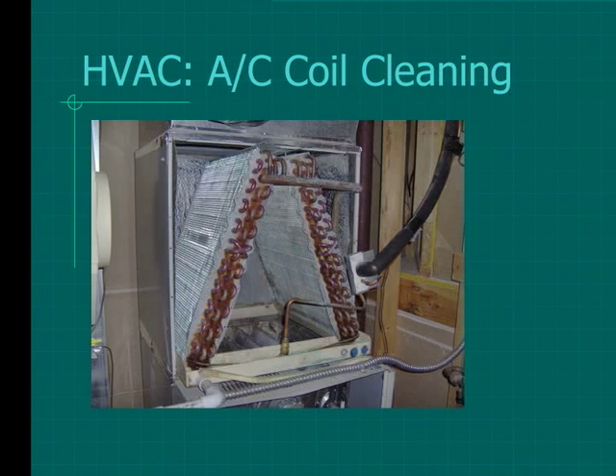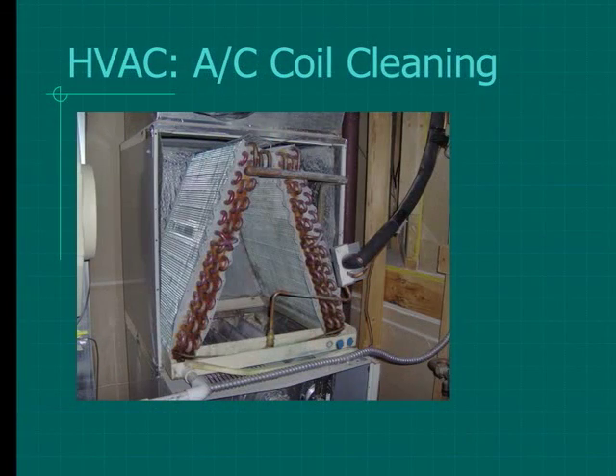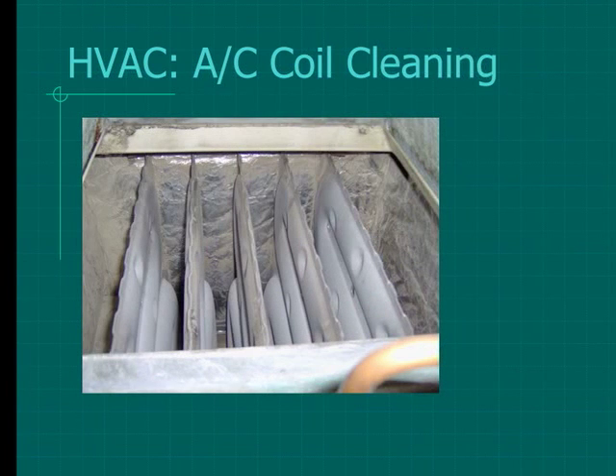Again, this is after it's cleaned. This is dirty. And this air conditioning coil is plugged up. We measure pressure in the audit, and the pressure went from 0.42 to 0.39 after it was cleaned. It should have been down at 0.26. So that's why we took it apart to take these pictures. So there's a picture of the cleaned coil.